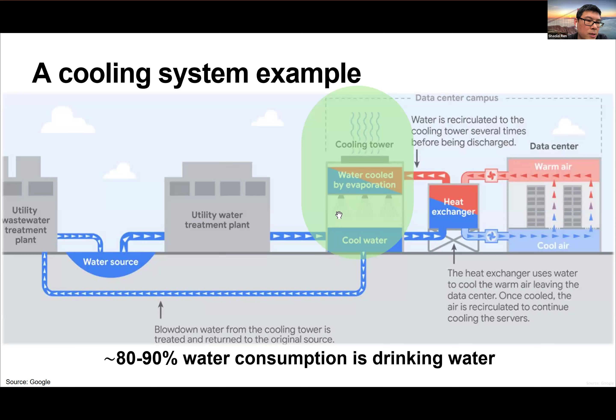For residential settings, we typically don't actually consume much water, although we withdraw a lot. For example, when we take a shower, we're using a lot of water, but that's water withdrawal. On average, for an urban residential setting, only 5 to 15% of the water we withdraw is considered water consumption. But in contrast, data centers typically evaporate 50 to 80% of the water they withdraw. So in some sense, they are consuming more water even though they might be withdrawing the same amount as residential customers.